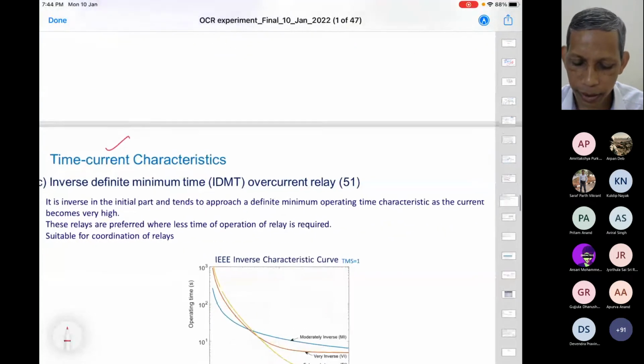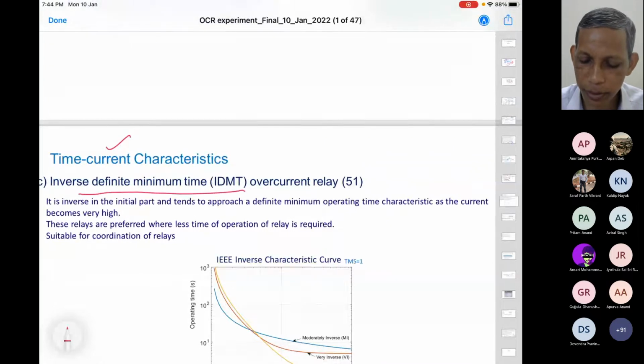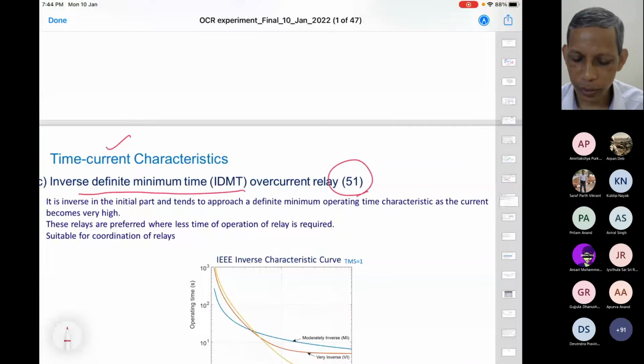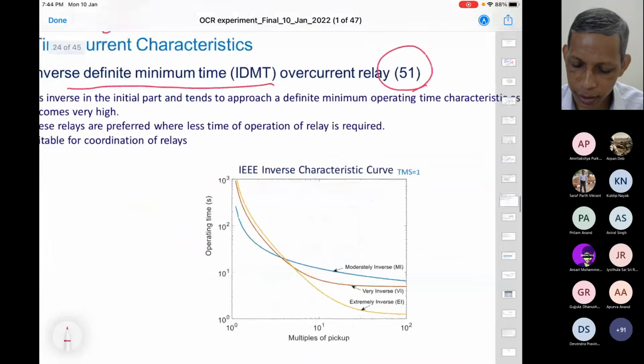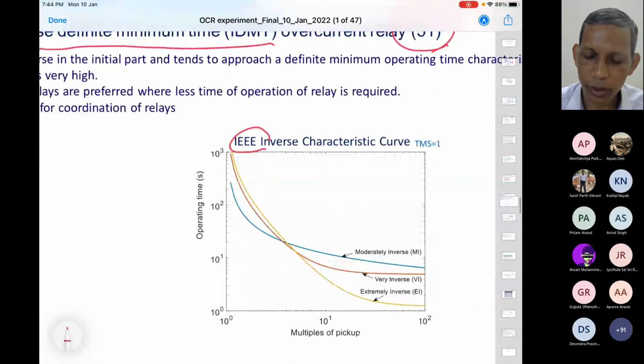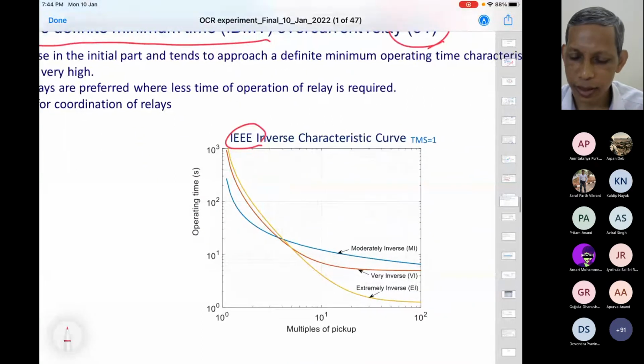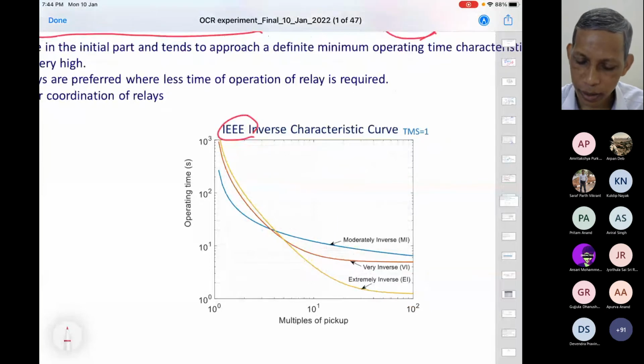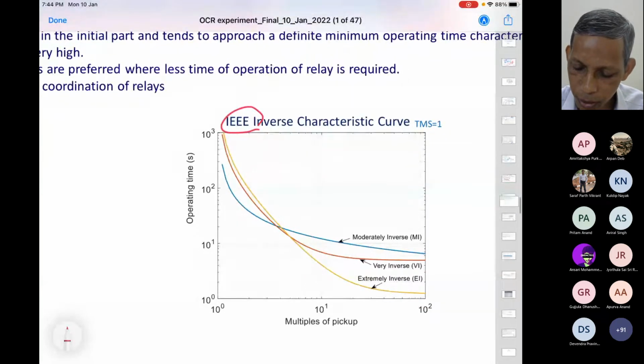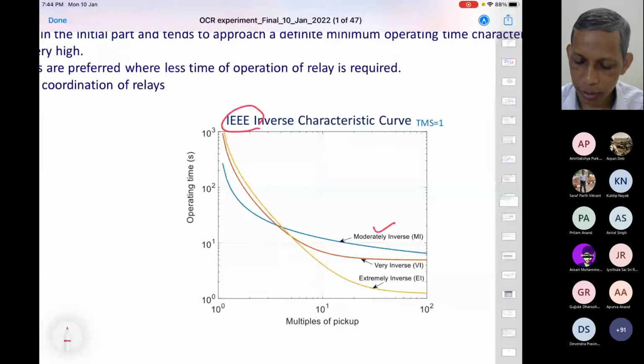Now we talk about inverse definite minimum time, or 51. You see here there are three curves. This is the IEEE curve. There are different standard agencies, and accordingly different curves. We call them moderately inverse, very inverse, and extremely inverse. You see here extremely inverse is the lower curve, very inverse is the middle curve, and moderately inverse is the upper curve.